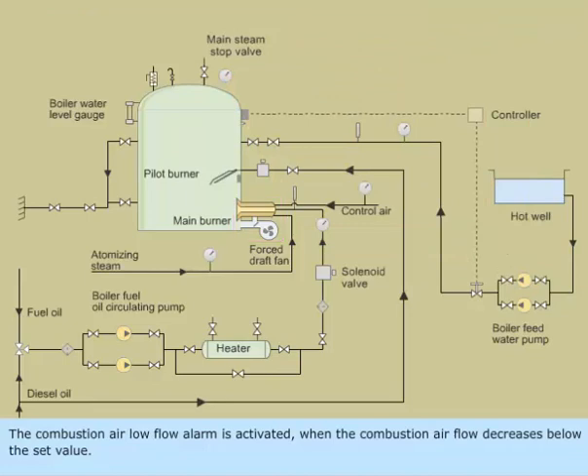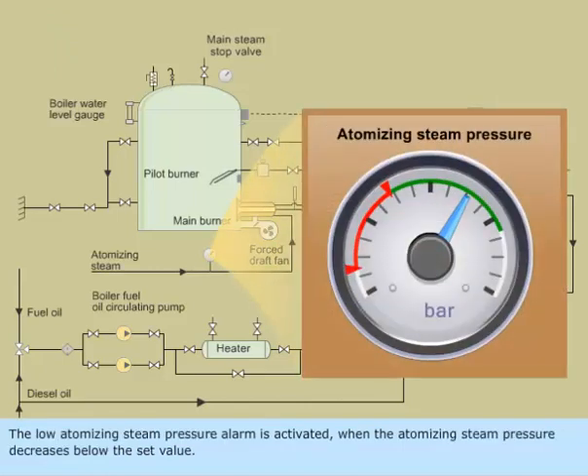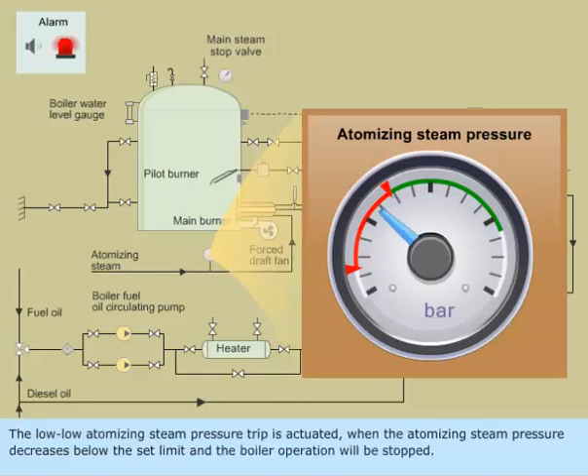The Combustion Air Low Flow Alarm is activated when the combustion air flow decreases below the set value. The Low Atomizing Steam Pressure Alarm is activated when the atomizing steam pressure decreases below the set value. The Low Low Atomizing Steam Pressure Trip is activated when the atomizing steam pressure decreases below the set limit and the boiler operation will be stopped.